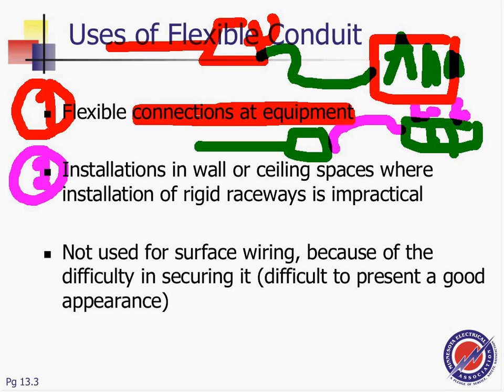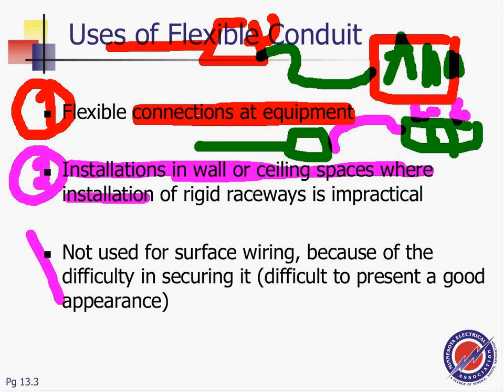If you want to fish a conduit in a wall, so in walls and ceilings, installation, if you fish a conduit in a wall, not a cable, a conduit, fishing an EMT or rigid or PVC might not be the best way of doing business. It's hard. So sometimes using them for remodeling, fishing conduits in a wall, they come in handy, though it's hard to work with them really, unless it's for short distances. You can't fish them in a wall and go 50 feet and pull the conductors on them. Good luck trying to get the conductors through. Pulling fish in the wall, that's another one.